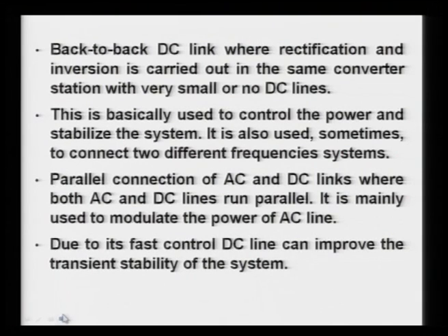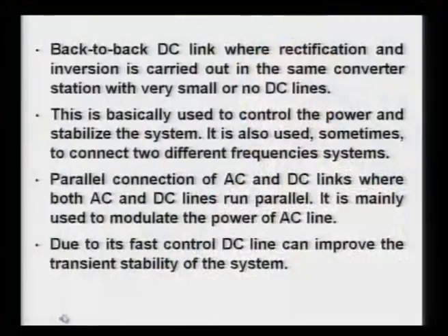It can also sometimes be used to connect two different frequency systems. We can also use AC and DC in parallel to stabilize the AC system by modulating the power over the AC lines. This is also a very fast control, the DC control lines are there, and thereby we can reduce the fault level, and also achieve fast clearing time with the HVDC system.